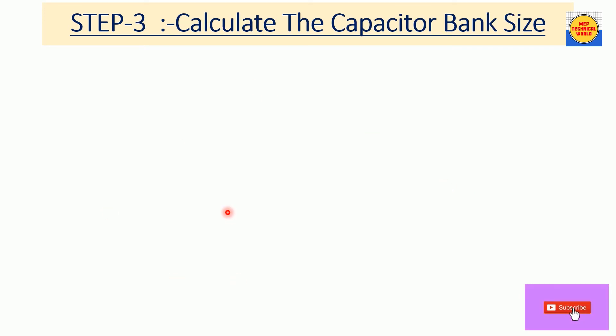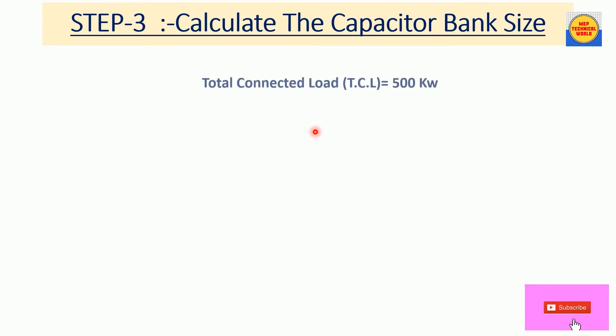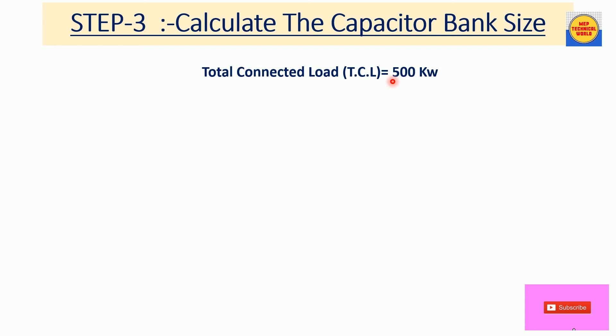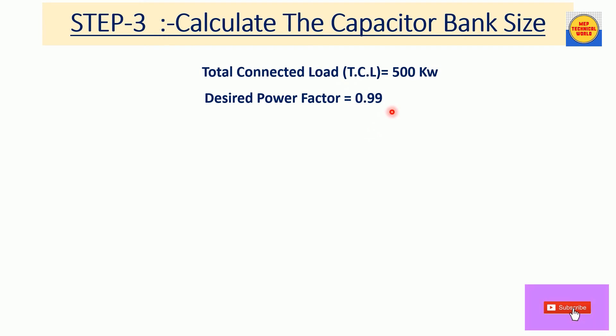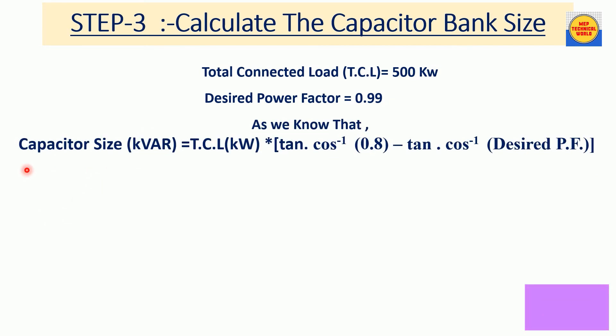Now move to Step 3. In this step, using the total connected load and the desired power factor value, we are going to calculate the capacitor bank size. We have total connected load of 500 kW from Step 1, and desired power factor of 0.99 from Step 2. You can change the desired power factor value as per your requirement.